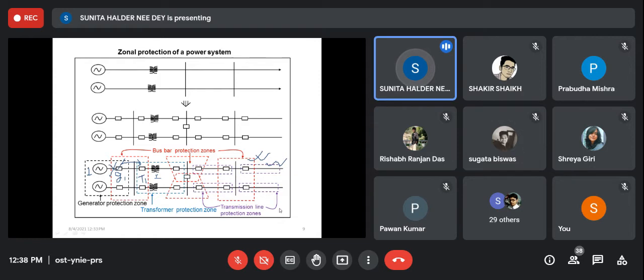Yes, ma'am. That's why I have told relay can operate depending on how you set it. Say you are protecting a semiconductor device, a station connecting a semiconductor device, say a solar power generating system. Then this is very costly. You do not want to take any risk for that. Then you can set the relay protecting that portion by that sensitivity. That is a sensitivity issue. That means if there be any instantaneous peak, within half cycle it will go. Half cycle means 20 millisecond is one cycle, so within 10 millisecond it will go.